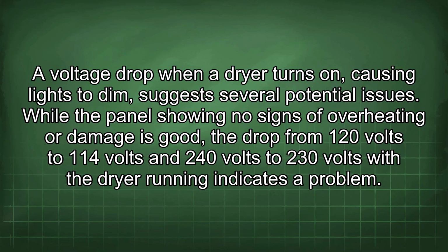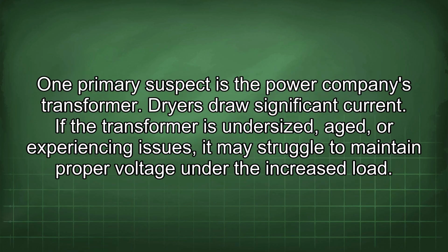A voltage drop when a dryer turns on, causing lights to dim, suggests several potential issues. While the panel showing no signs of overheating or damage is good, the drop from 120 volts to 114 volts and 240 volts to 230 volts with the dryer running indicates a problem. One primary suspect is the power company's transformer.